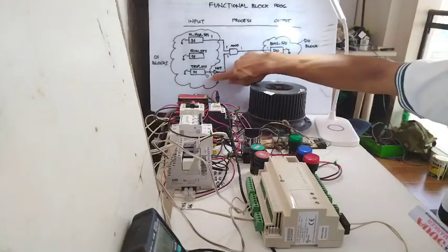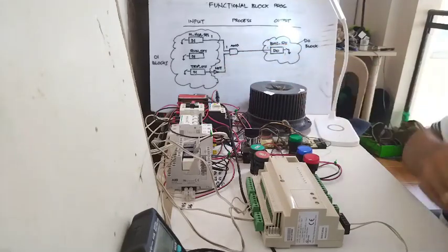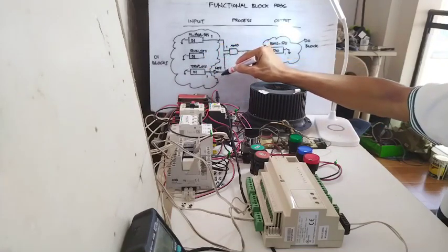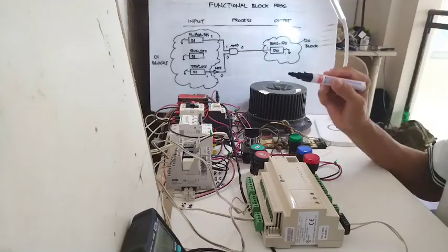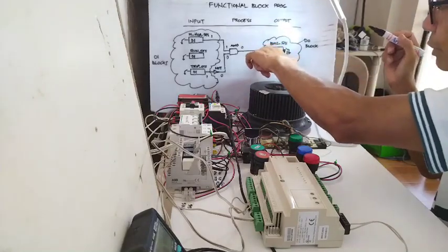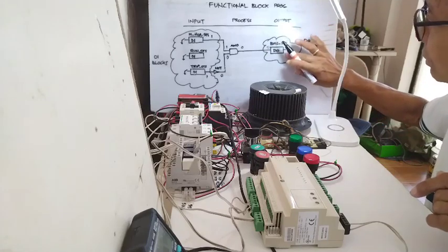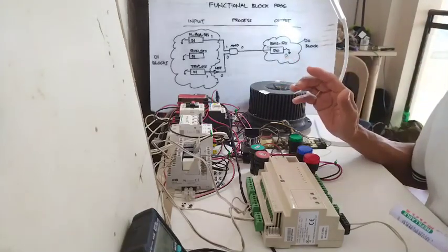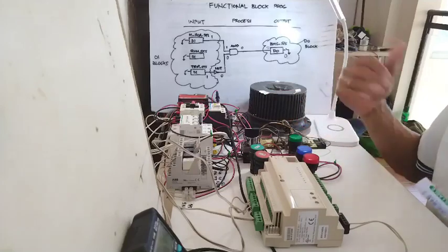Now let's trace what happens if it trips. Assuming it is running and then it trips — this trip signal becomes 1 because it tripped and the contact closes. Then the NOT gate output becomes 0. Then the AND gate output becomes 0, because both inputs must be 1 for a 1 output. So the output is 0, and our BMS releases the command to the control panel.